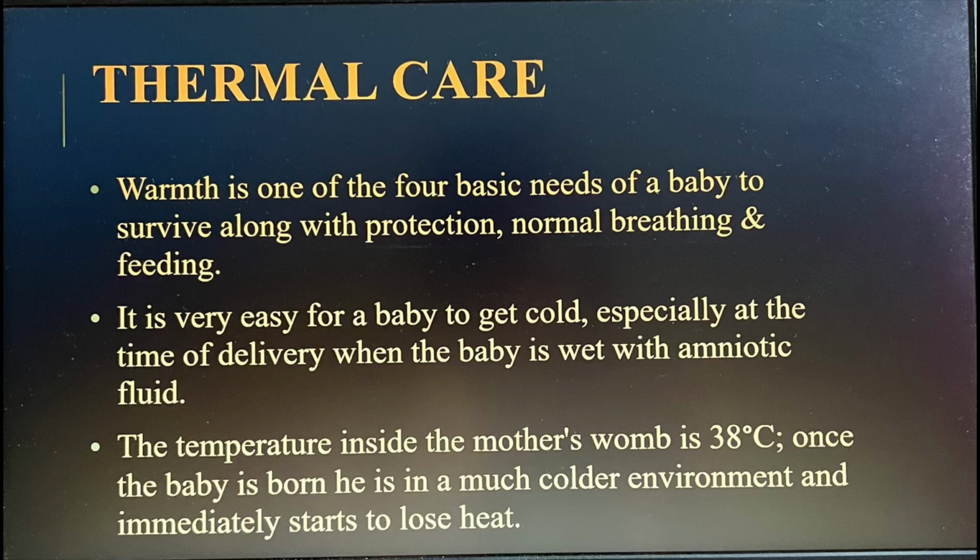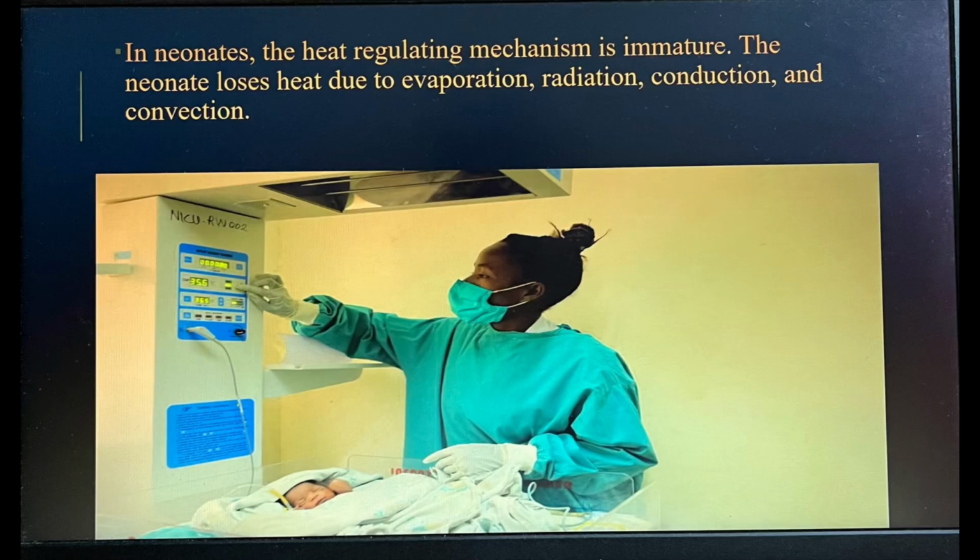We can start with KMC, that is kangaroo mother care, with skin to skin contact with the mother, or else we can keep the baby in the radiant warmer. Half an hour before the delivery of the baby, we have to switch on the radiant warmer in manual mode. About the radiant warmer settings and parts I will discuss in a different video, but in this video I will only tell about the modes.